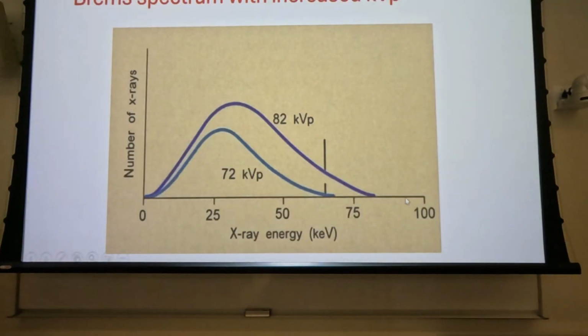So this is where last year's became inaccurate. So with the bremsstrahlung spectrum, what you notice is that we get an increase in the lower energy X-rays, but it's not until we get to the upper region of the lower kVp that we really see the increase. The area under the bubble represents just numbers, kind of like mass, if you want to draw an analogy there. So we've got a significant change in numbers. We've got a significant change in the peak energy. And then we've also got a push of the height of the bubble, which represents about the peak energy and the average energy, towards a higher energy side. So we get a change in all the imaging characteristics.